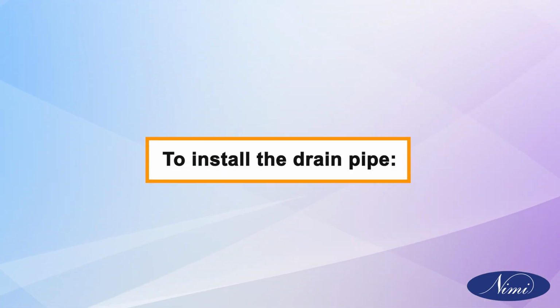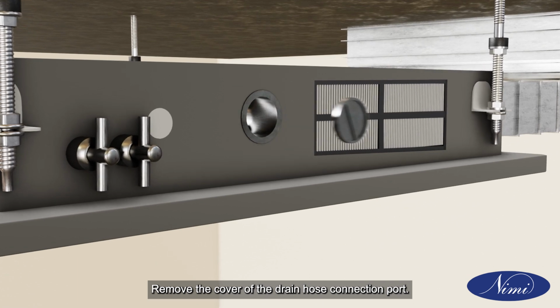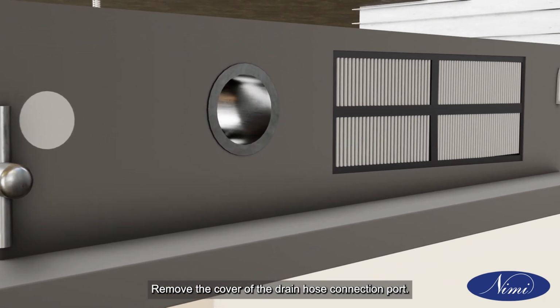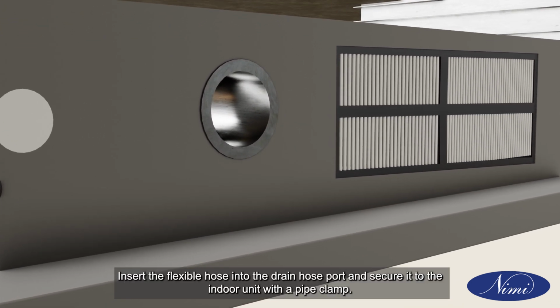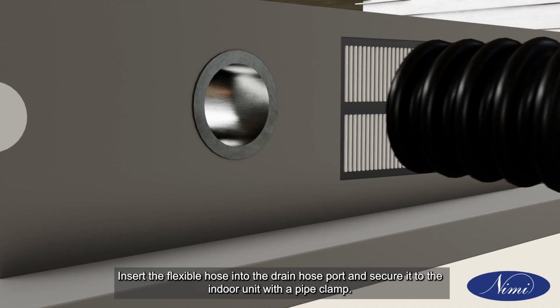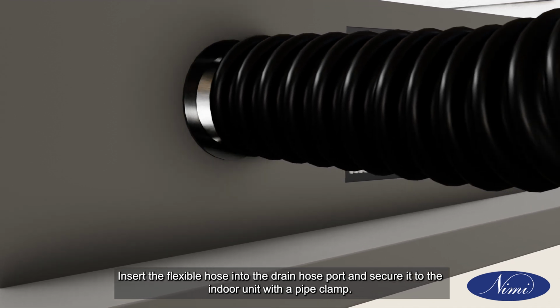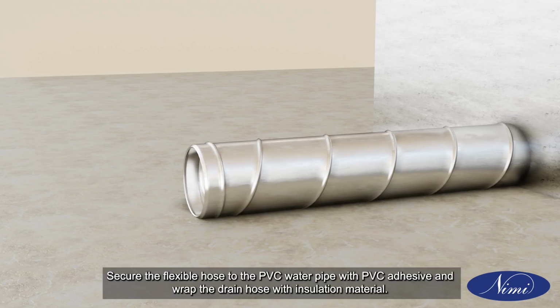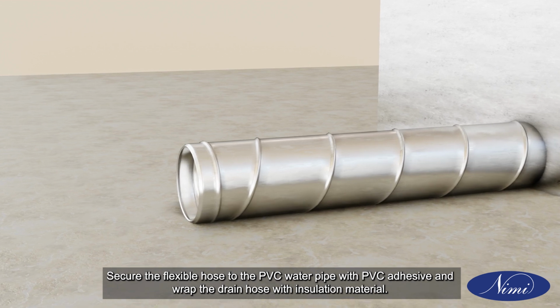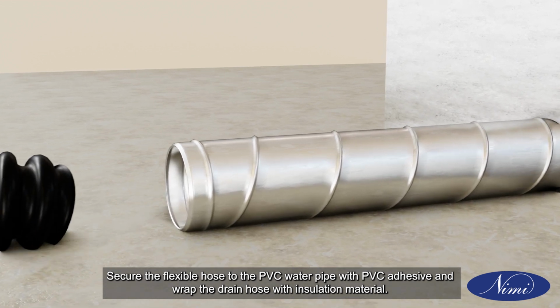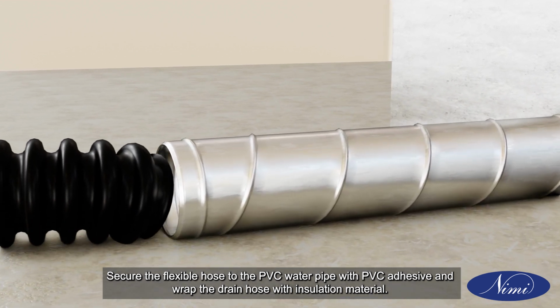To install the drain pipe, remove the cover of the drain hose connection port. Insert the flexible hose into the drain hose port and secure it to the indoor unit with a pipe clamp. Secure the flexible hose to the PVC water pipe with PVC adhesive and wrap the drain hose with insulation material.